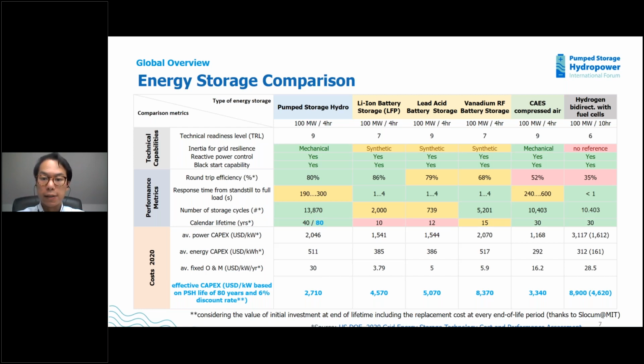But if you take into account the long lifetime of pump storage, which from industry experience can be over 80 years, and apply a 6% discount rate, you will see that the effective capex of pump storage is almost half that of battery storage over 80 years, as batteries need to be replaced every 10 years.